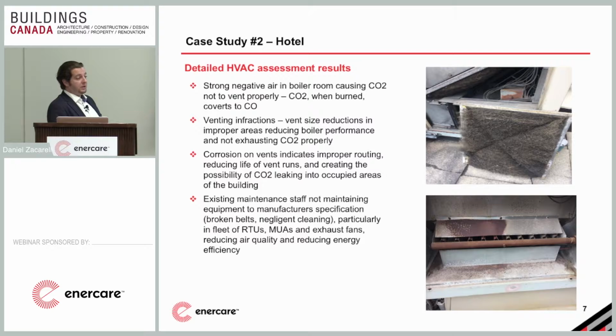One of the more serious ones is in their boiler room, they had a bad negative air problem. And these boilers are older boilers, atmospheric. So as they were not venting properly, the negative air was sucking the CO2 back into the room. When CO2 comes back into the room, it drops down. These boilers, being old atmospheric boilers, breathe in from the bottom. If they breathe in that CO2 and it's part of that combustion procedure, it turns into carbon monoxide. And carbon monoxide, as we all know, is very deadly.